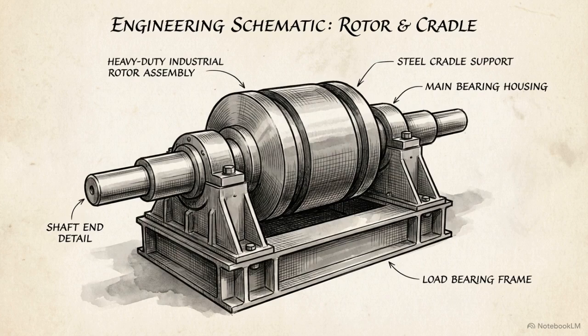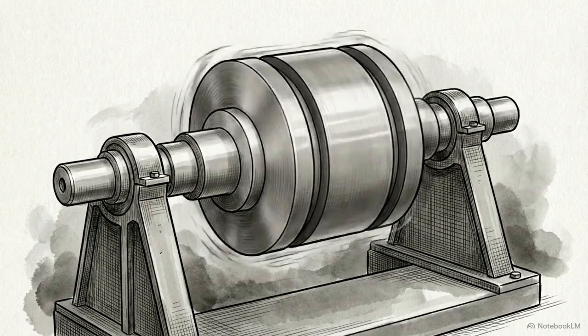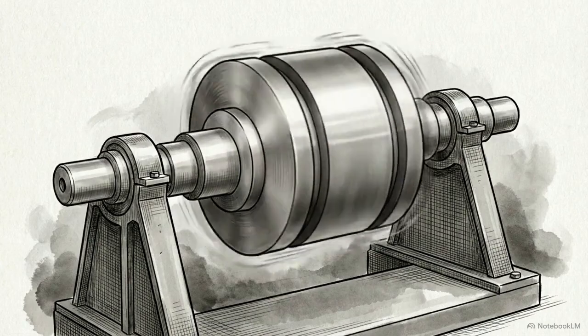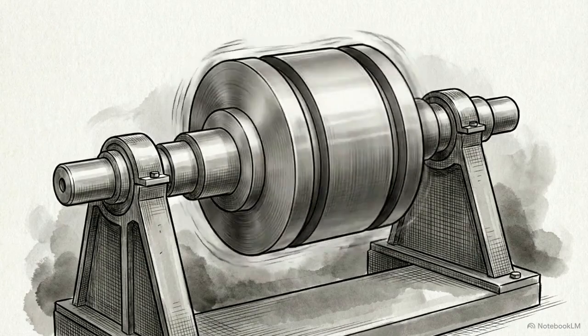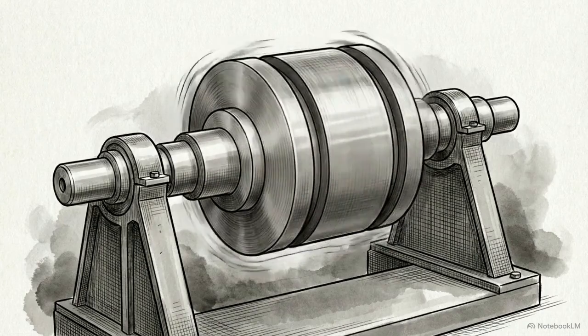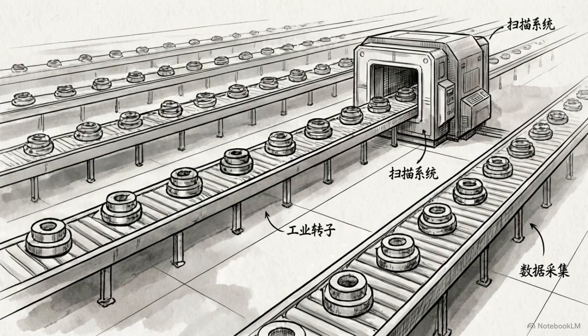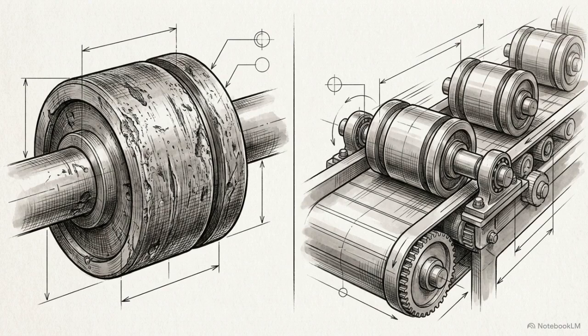This approach has an advantage. If you have a rotor that is wildly off balance straight off the manufacturing line, the rigid structure simply absorbs the violent shaking. You don't need any pre-balancing operations. It also bypasses the trial weight method. Without the need to self-calibrate for every single test, the operator can churn through testing cycles rapidly. The hard-bearing system trades mechanical gentleness for raw processing speed.